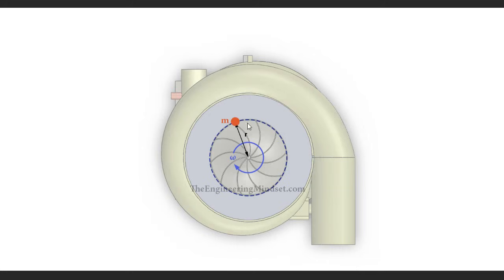Now let's imagine we've got a particle, a ball of refrigerant, and it's sitting just at the very edge of the impeller, just as it's about to be thrown off and chucked through the diffuser and into the volute. This is the point where the maximum centrifugal force is applied to this mass. So that's the point of interest and what we want to focus our formulas on.